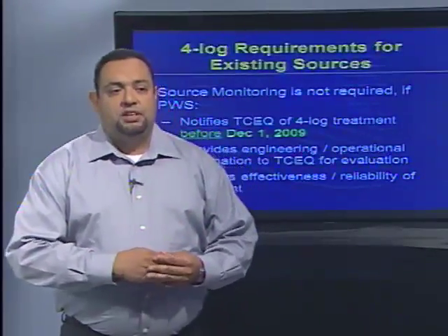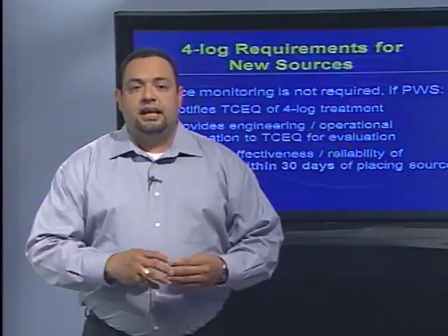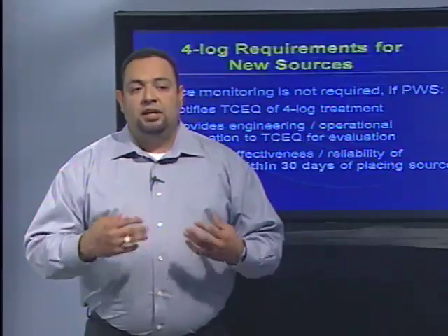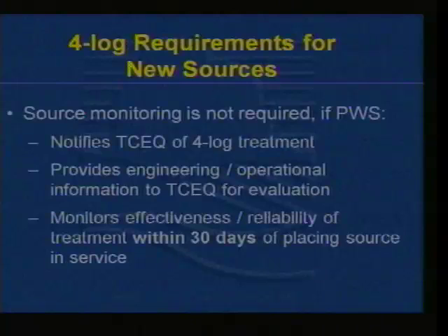So 4-log requirements for new sources, the next slide I'll cover. In this case, the only thing different from the prior slide is that you have to be monitoring the effectiveness and reliability of treatment at least 30 days prior to placing your well online. And so that's the important key difference between those two slides: for new sources, you've got to be checking the effectiveness and reliability of your treatment for up to 30 days prior to placing that source into service. And the next slide.